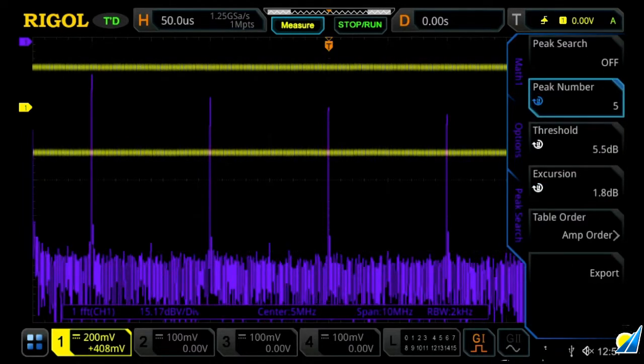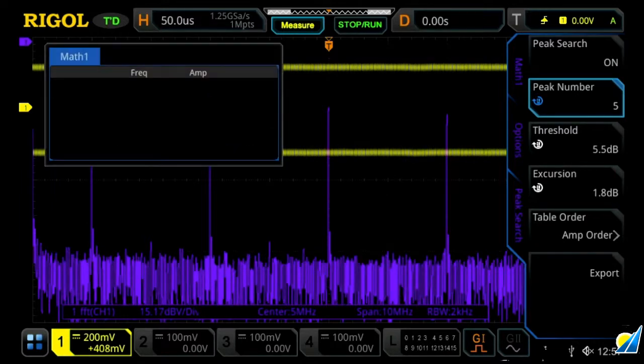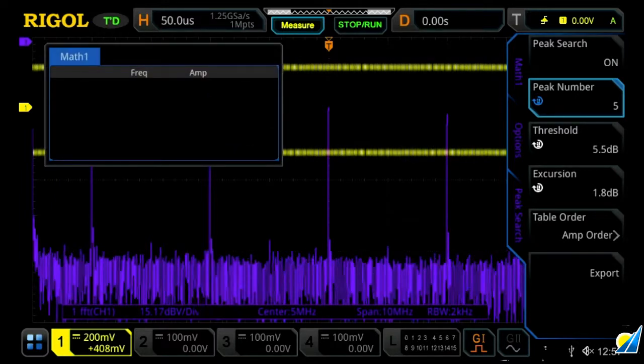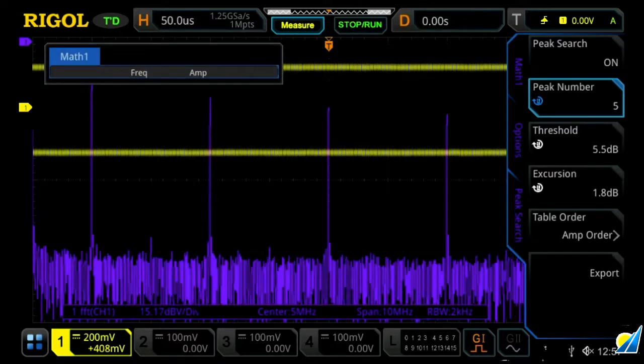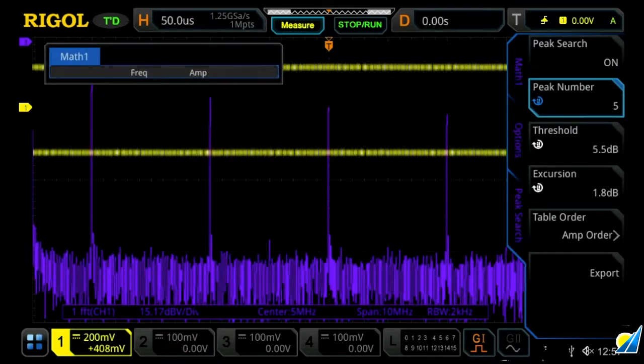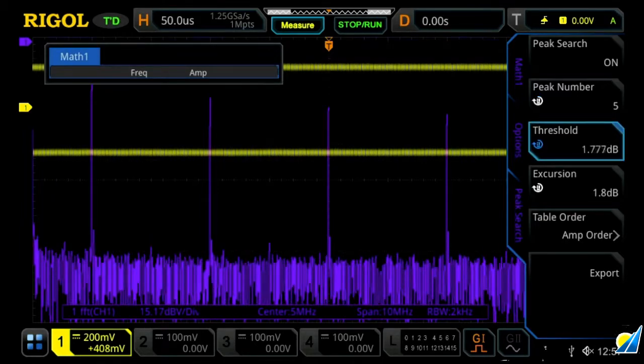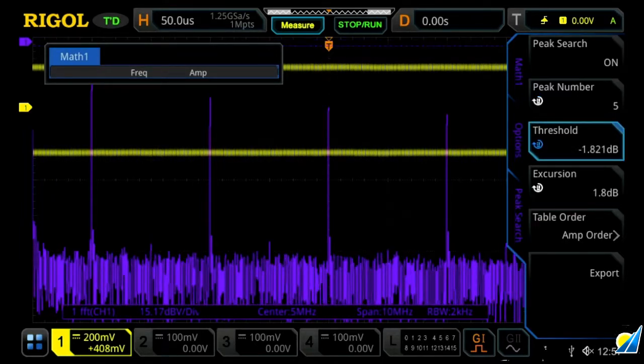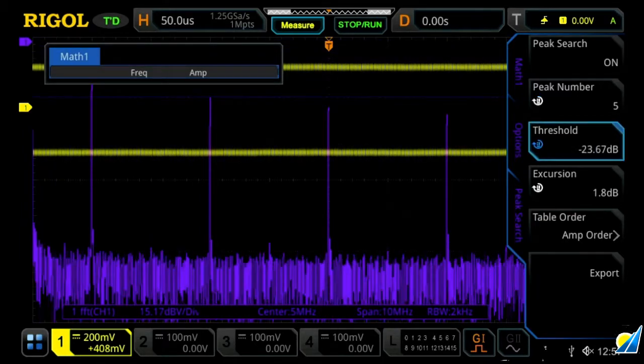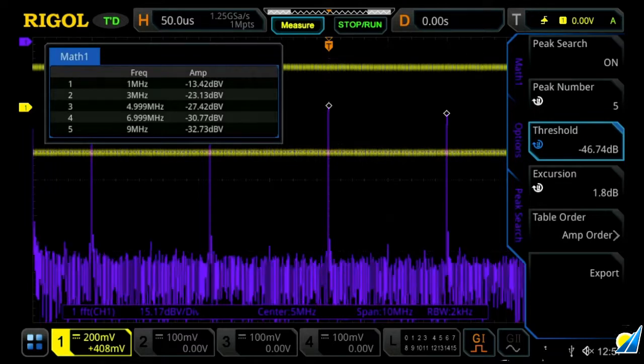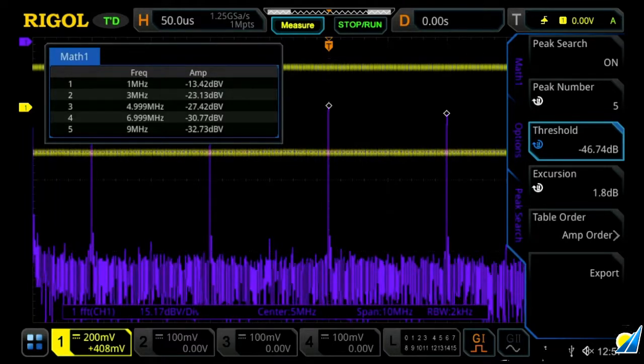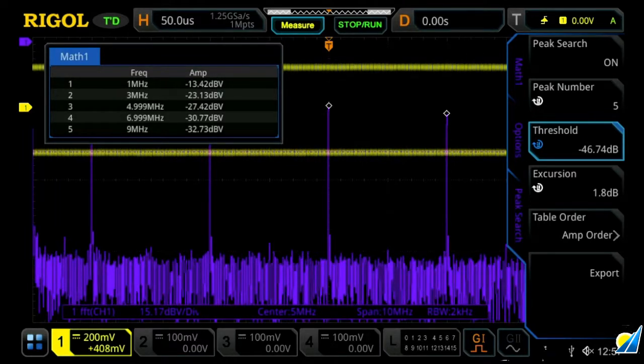But we can now go into our peak search, which allows you to easily find multiple peaks. In order to do that, you first turn it on, then you go threshold, and then you're basically setting a trigger point with this dotted purple line. And once it's below, you'll see your five peaks being displayed on the screen.